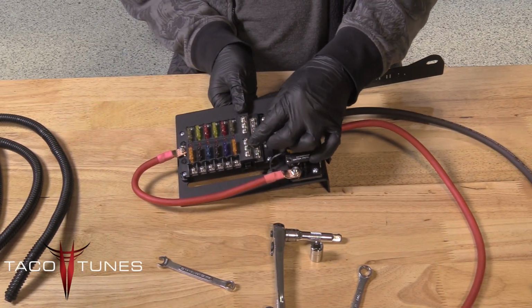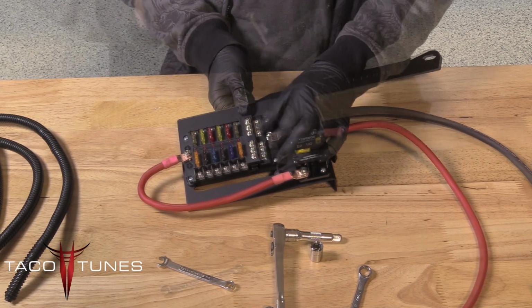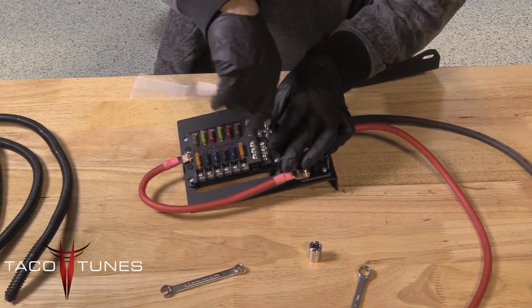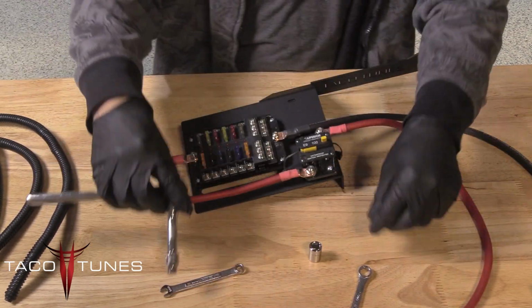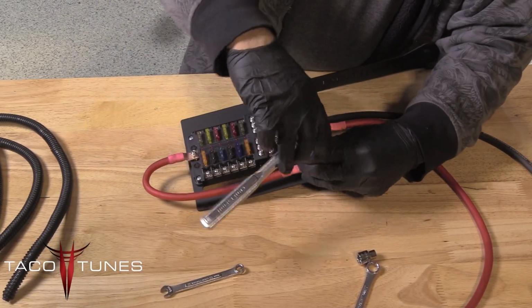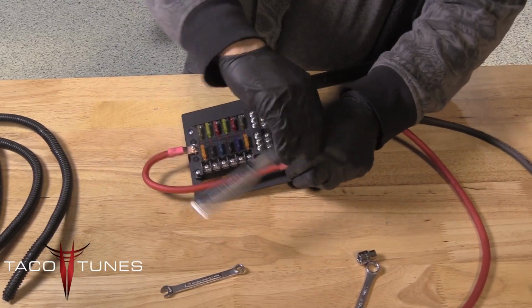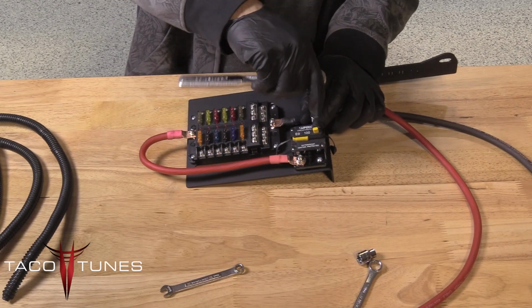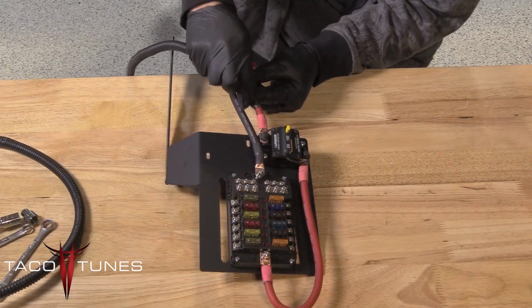This next step is really important. Good tight connections are essential for good power flow. If available, tighten the fuse block to 2.25 foot-pounds, and the fuse holder and circuit breaker to 3.2 foot-pounds. You want to get as tight as possible, but obviously you don't want to break the fuse holder or the circuit breaker.